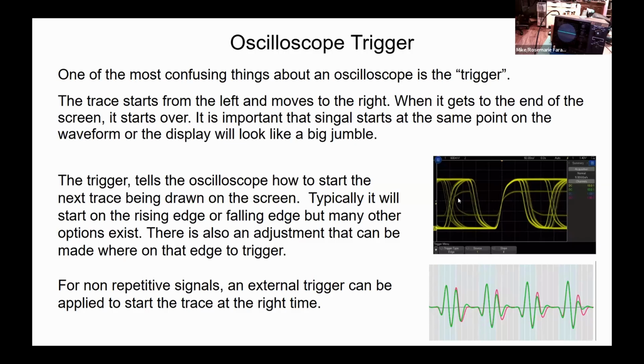A lot of times you'll be looking at, relative to the center line, what the positive and negative is, or maybe it starts at zero up here. So you'll be looking at this peak value, and then you're going to try to get it to sync. Sometimes you're going to have really complicated waveforms, something like this, and this can get a little bit difficult to sync because you've got a bunch of different rising edges. If we say sync on a rising edge, it's going to look for something negative, and when it starts to rise, it's going to sync. Well, it could sync on this one, it could sync on this one, could sync on this one. There's a lot of different spots it could sync on, and so you may see an ugly pattern like this because it's trying to sync on a repeated pattern, but maybe you don't have a repeated pattern.